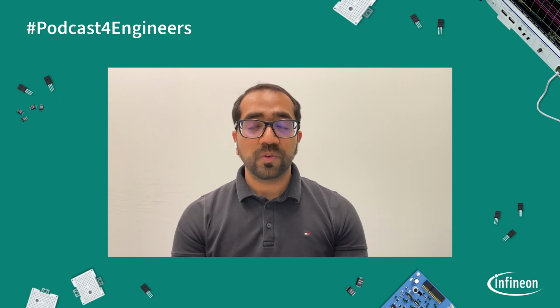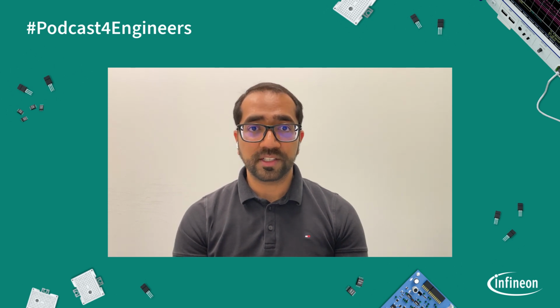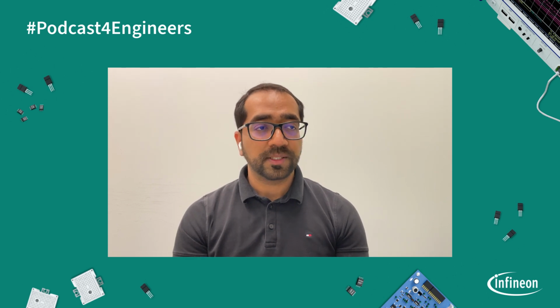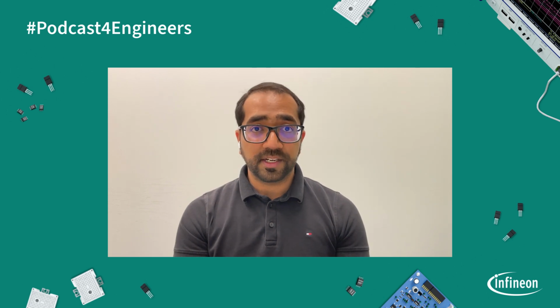Now, these GPUs work on a voltage of 0.8 to 1 volt. It's not feasible to supply 0.8 to 1 volt directly. So the traditional architecture was a 12 volt architecture, where 12 volts was converted to 0.8 volts, and the backplane was 12 volts. Now, as we know, there is a boom in AI. The machine learning models are getting more and more power hungry, and even the GPUs are getting more and more power dense. The industry moved towards a 48 volt architecture.